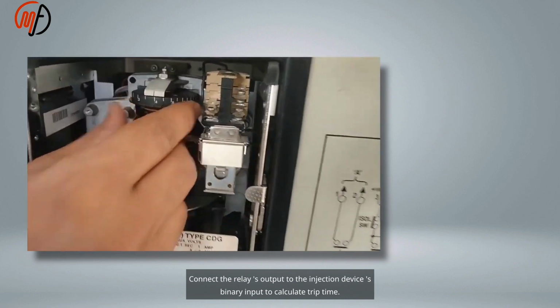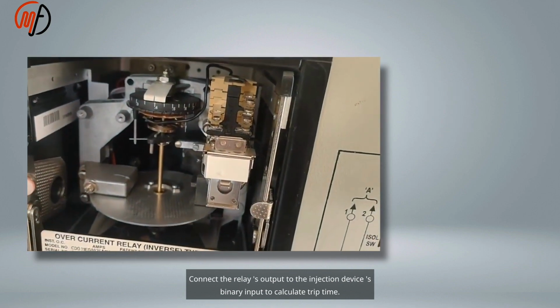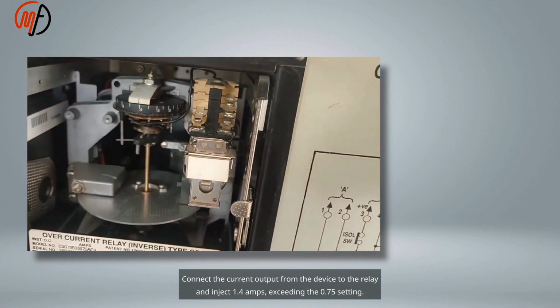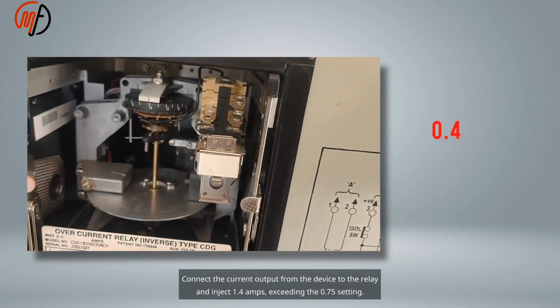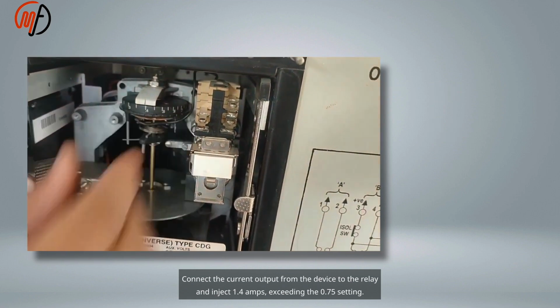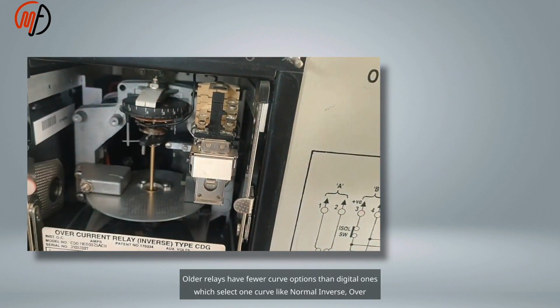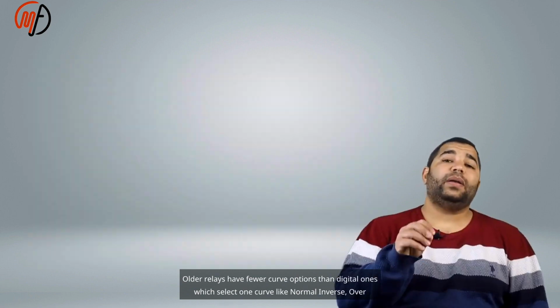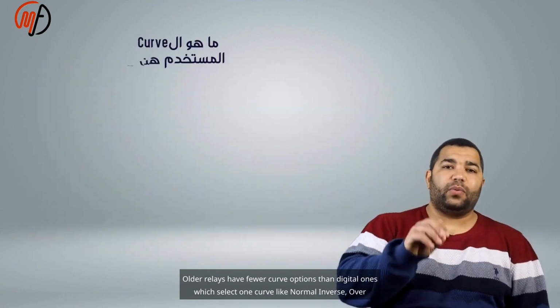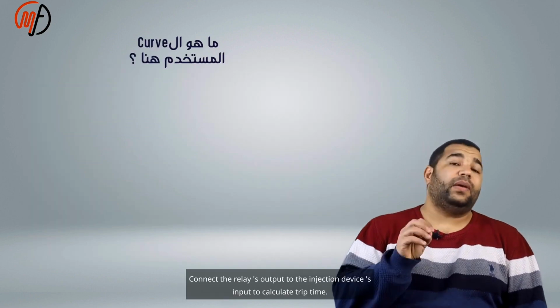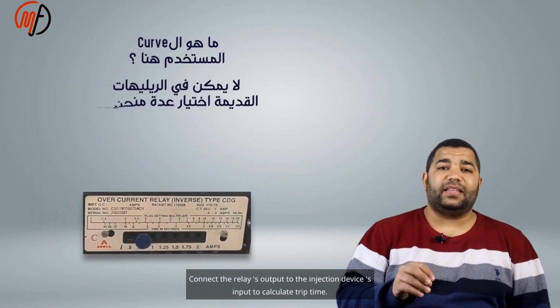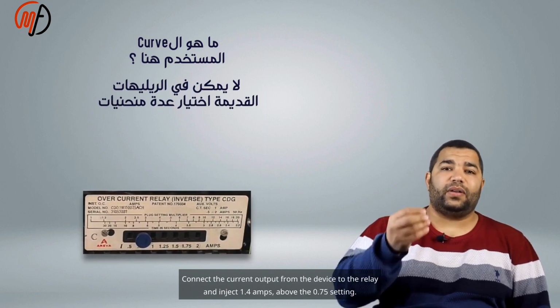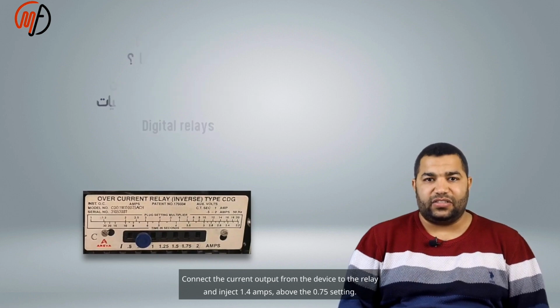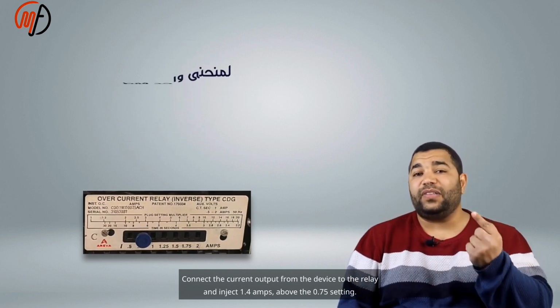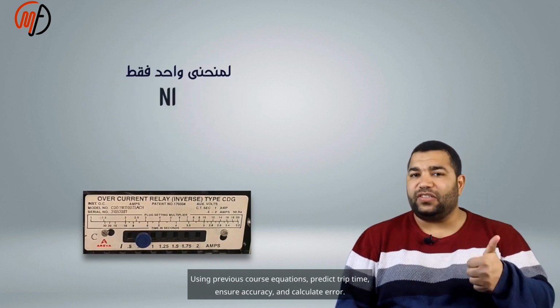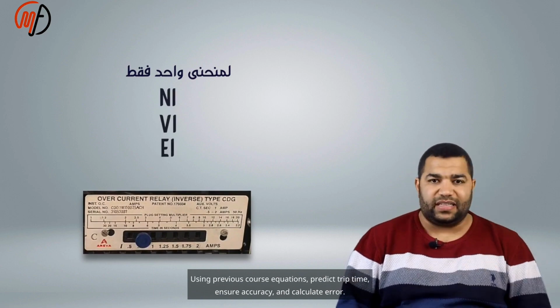Connect the relay's output to the injection device's binary input to calculate trip time. Connect the current output from the device to the relay and inject 1.4 amps, exceeding the 0.75 setting. The TMS can be selected from 0.1 to 1. Older relays have fewer curve options than digital ones, which select one curve like normal inverse, very inverse, or extremely inverse. Using the previous course equations, predict the trip time, ensure accuracy, and calculate the error.